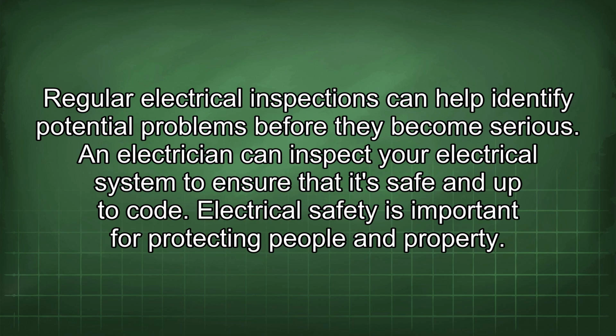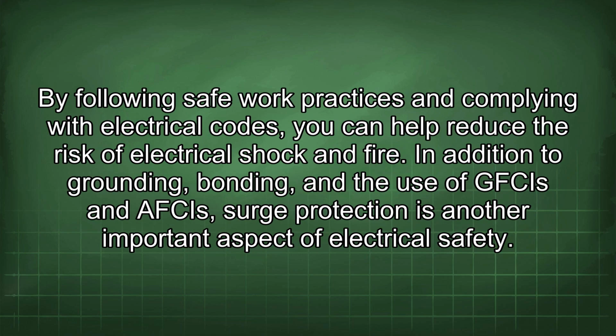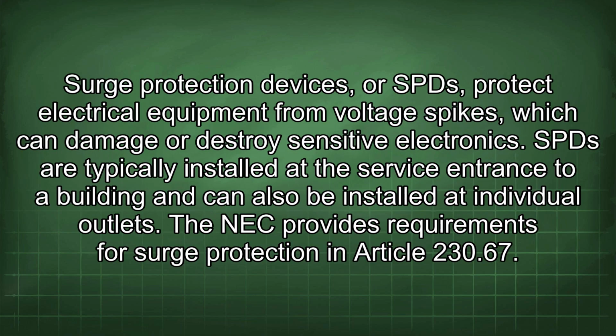Electrical safety is important for protecting people and property. By following safe work practices and complying with electrical codes, you can help reduce the risk of electrical shock and fire. In addition to grounding, bonding, and the use of GFCIs and AFCIs, surge protection is another important aspect of electrical safety. Surge protection devices, or SPDs, protect electrical equipment from voltage spikes, which can damage or destroy sensitive electronics. SPDs are typically installed at the service entrance to a building and can also be installed at individual outlets.